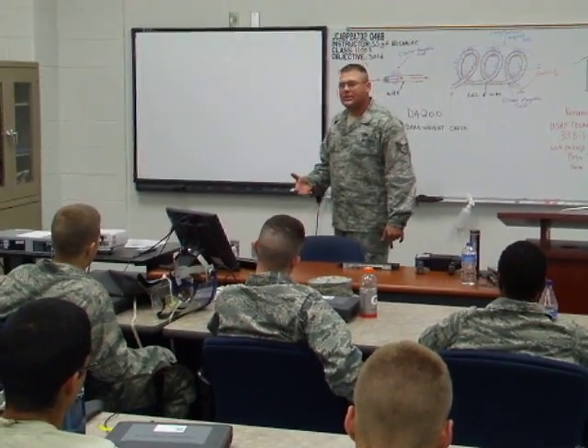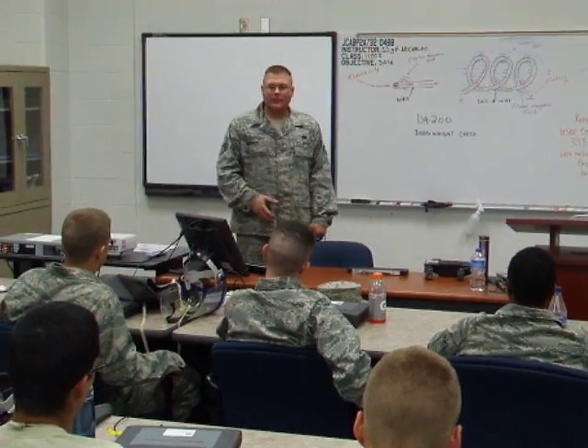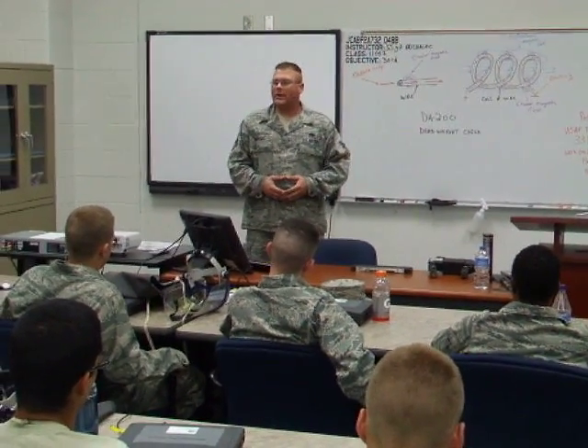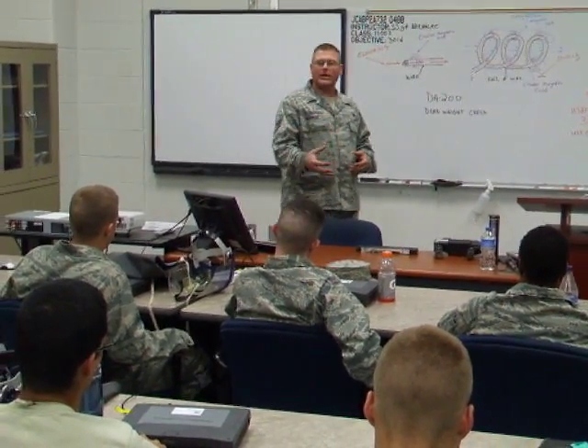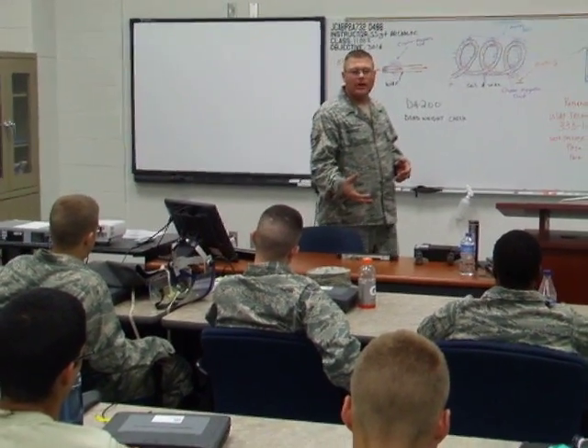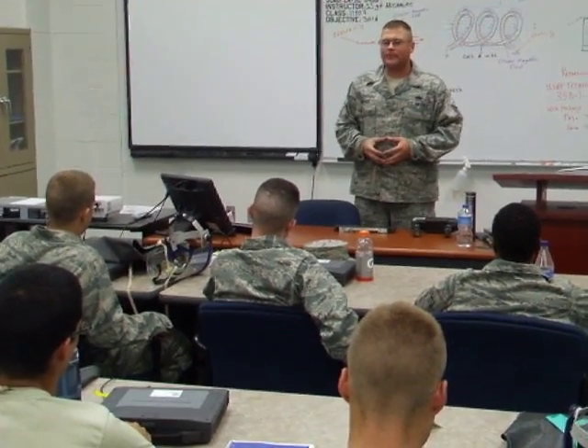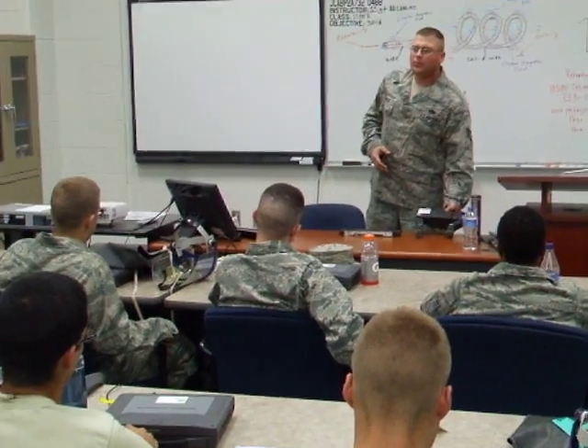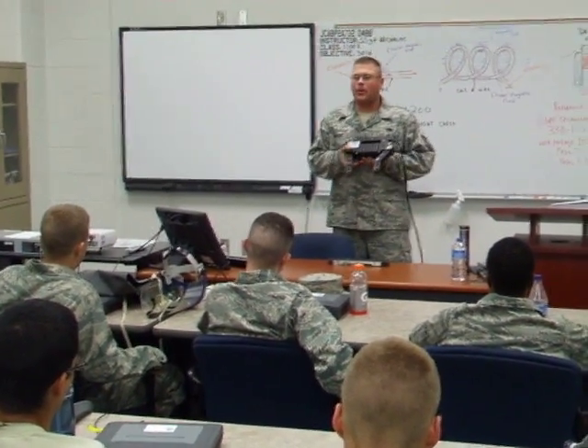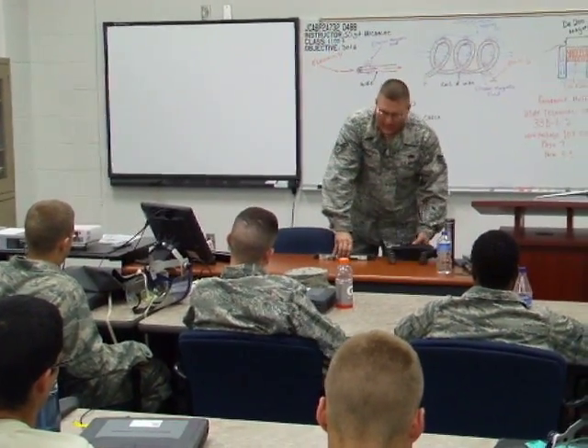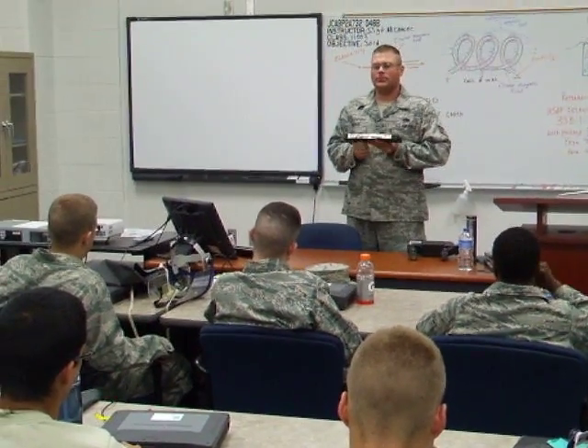Now, this material states that we have to do a deadweight check. Basically what that's telling us is that our alternating current magnetic field is strong enough to pick up 10 pounds of weight. The two items we're going to be using to perform this inspection are the DA200 Parker probe, as well as a 10-pound manufactured weight.